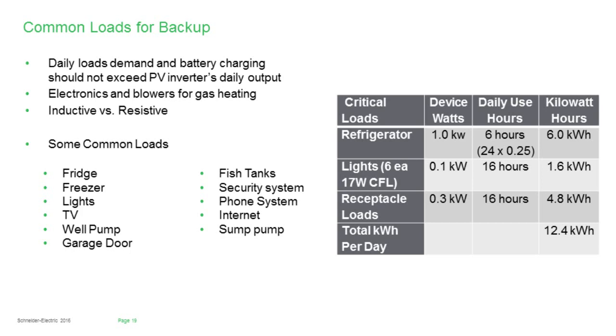For the refrigerator, as an example, it's a 1 kW load. But when sizing out the system, we have to remember the fridge maybe only runs for 15 minutes an hour, which is what that 0.25 represents. So really it's only about a 6-hour load, or 6 kilowatt hours of consumption. Just something to keep in mind.